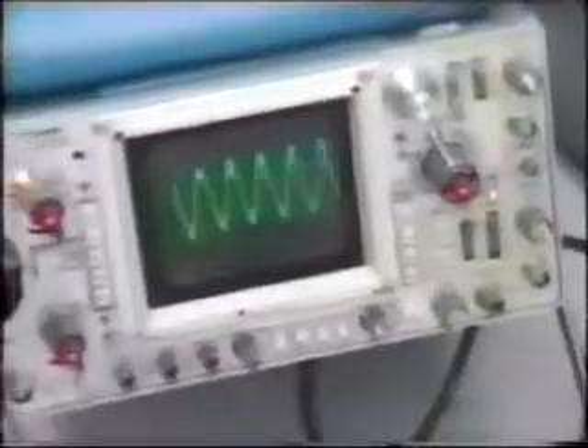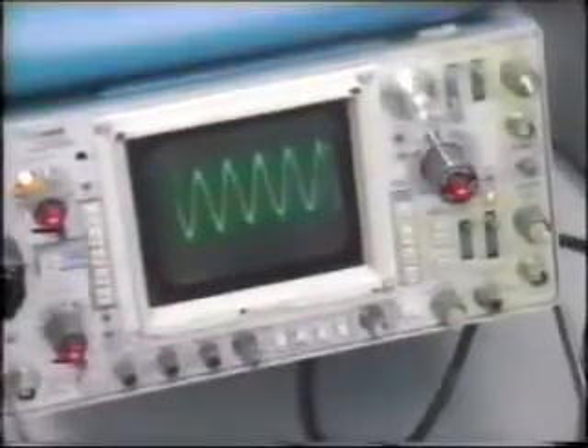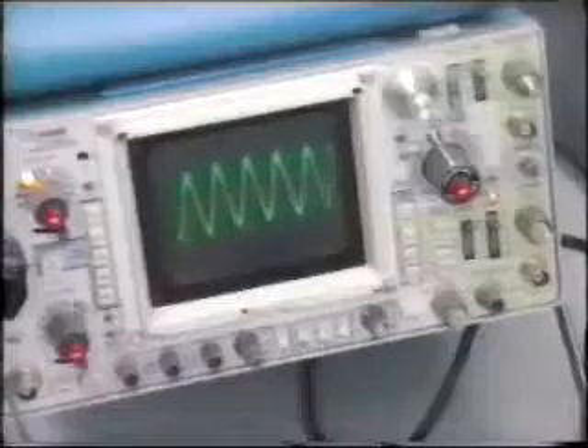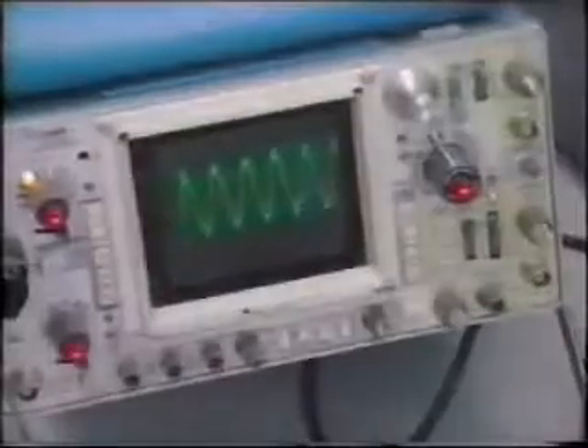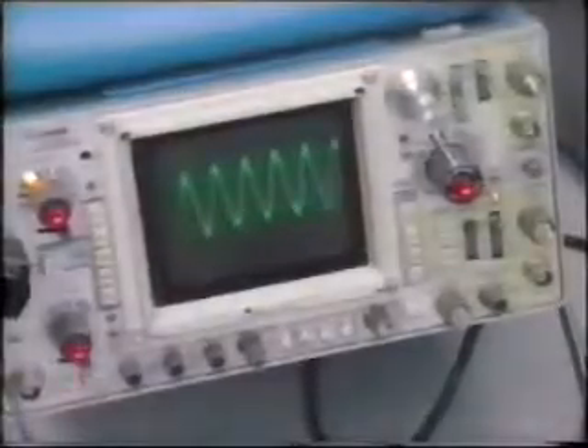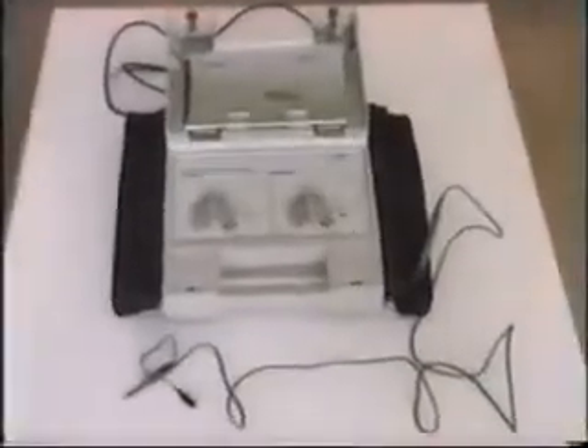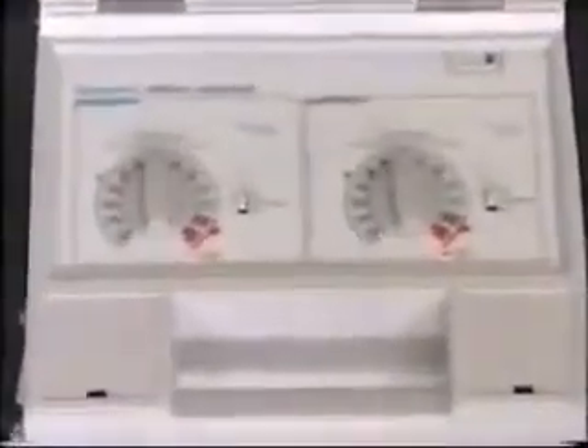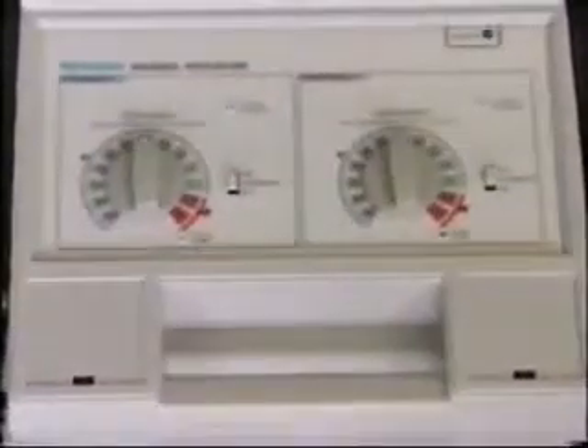On a telephone circuit, it may cause common mode voltages to be coupled to the phone line via the scope, perhaps disrupting SCADA communications or causing unexpected operation on a pilot protection scheme. Whenever making tests on solid-state or telephone equipment, be sure to use some form of isolation, such as this input isolator, so as to isolate the scope probe from ground.